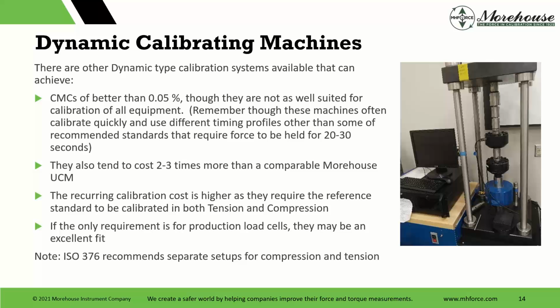They also tend to cost 2 to 3 times more than a comparable UCM. The recurring calibration cost is higher as they require the reference standard to be calibrated in both tension and compression. If the only requirement is for production load cells, they may be an excellent fit. If I'm manufacturing load cells for scales at $5-10, needing a commercial calibration, a quick check of nonlinearity and hysteresis, and I want to do 5 or more an hour, hopefully 10 or more, this machine might be an excellent fit. I can just put it in, run it, the technician can record the readings, and then fixture the next one in. Same setups, you can just bang out work. Really, really easy.